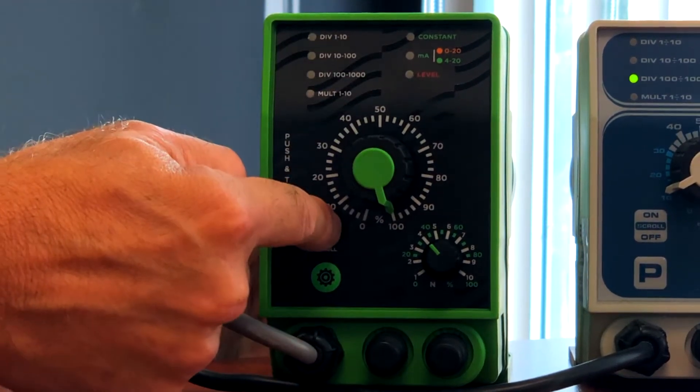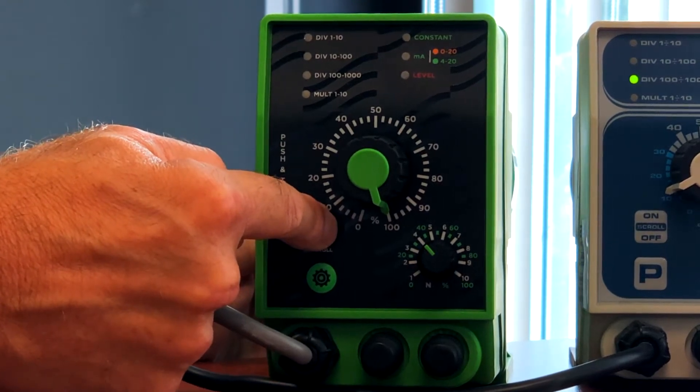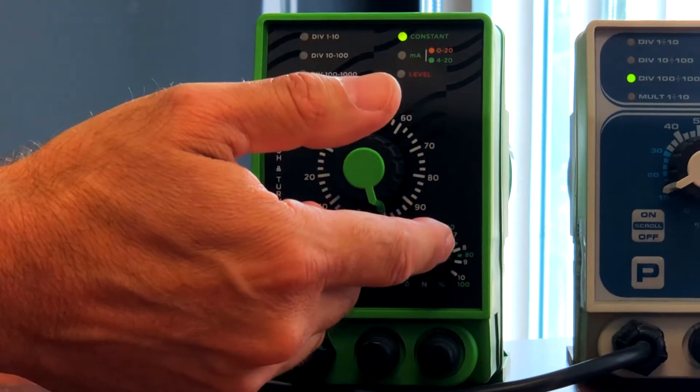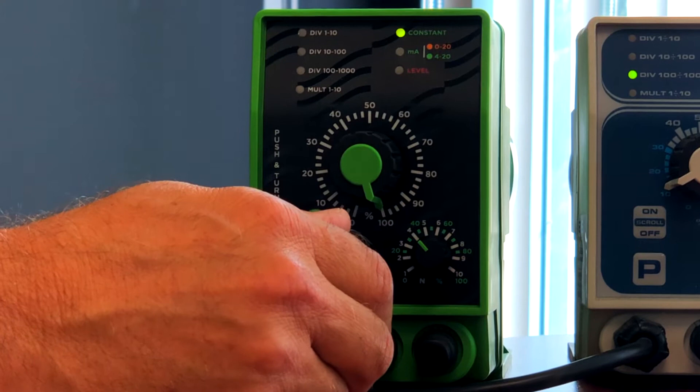Then I hold the button down for four seconds, the same button, and when the pump starts dosing, as you can see now, it's actually stroking at maximum capacity. It will run like that for 30 seconds until the pump primes.